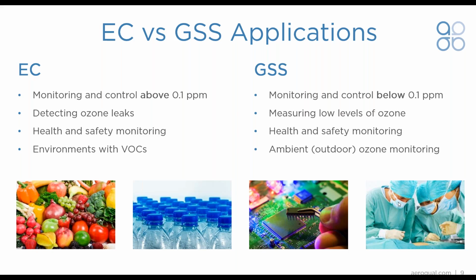By contrast, you've got the GSS sensor, and with its excellent accuracy and stability below 0.1 ppm, it's really the only option for health and safety applications, especially where you have regulations around the world moving towards continually lower exposure thresholds. When I say exposure thresholds, these are what you're exposed to when you're in the workplace or in the environment that you are working in.